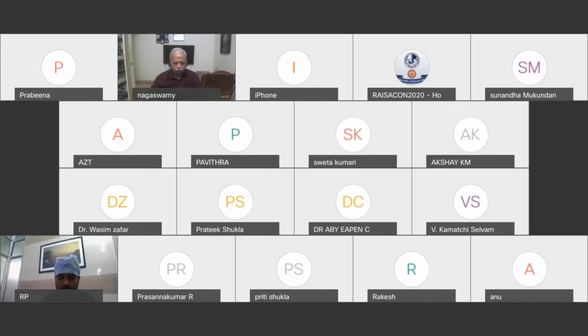An anesthesia workstation is a medical device used to generate and mix a fresh gas flow of medical gases and inhalational anesthetic agents for the purpose of inducing and maintaining anesthesia. Safety features included in the anesthesia workstation are, first, safety features for the OT personnel, which include anti-static rubber that prevents static electric transfer and prevents fires due to static electricity. Very good. And safety features for the patients, to prevent delivery of hypoxic mixtures.